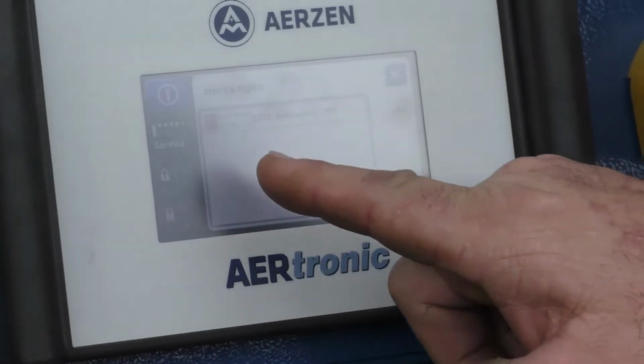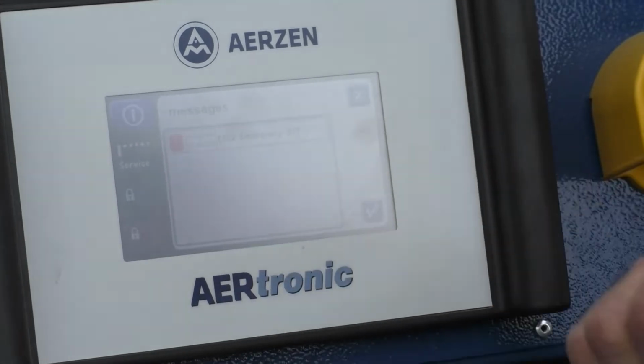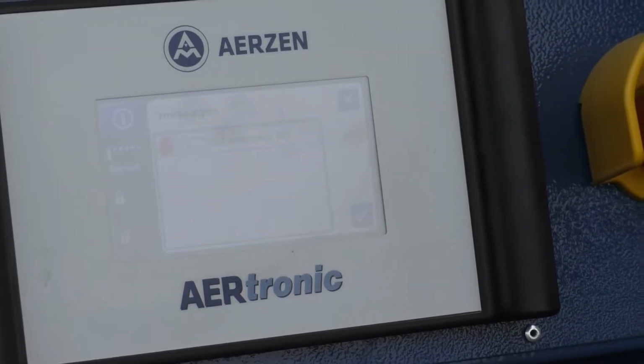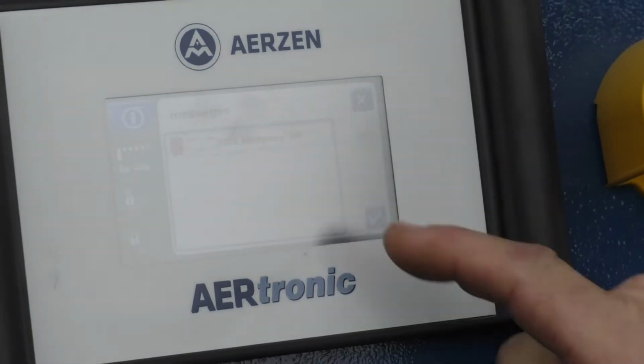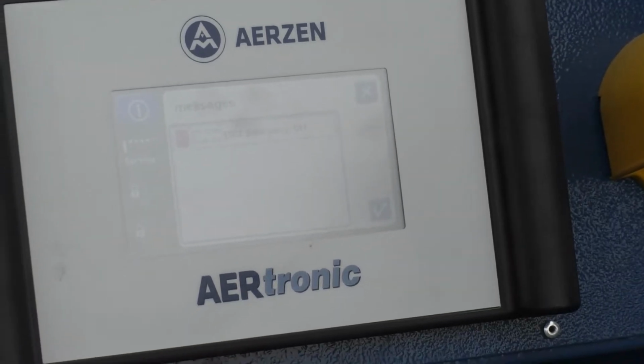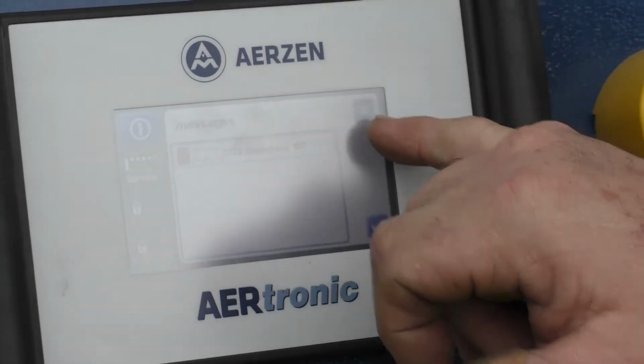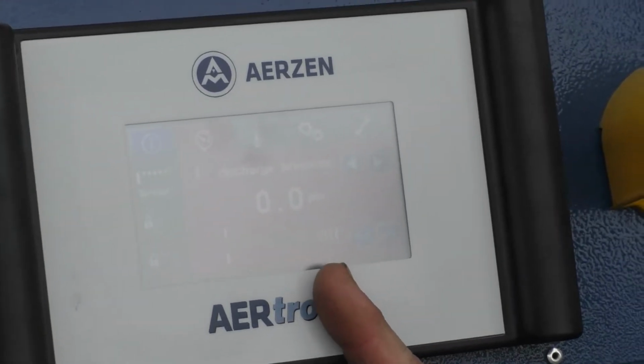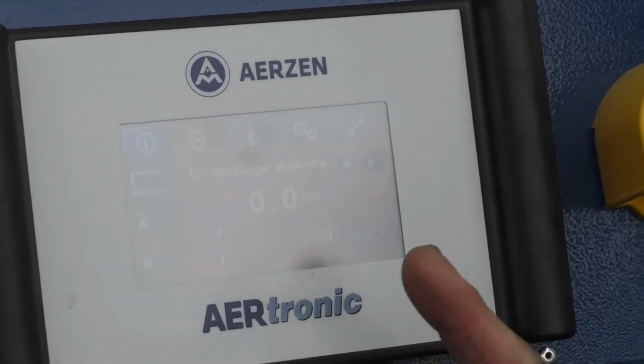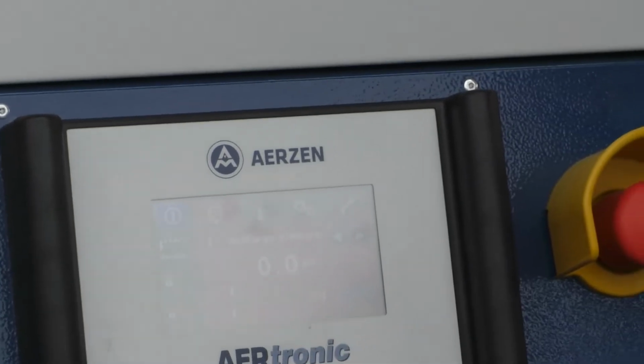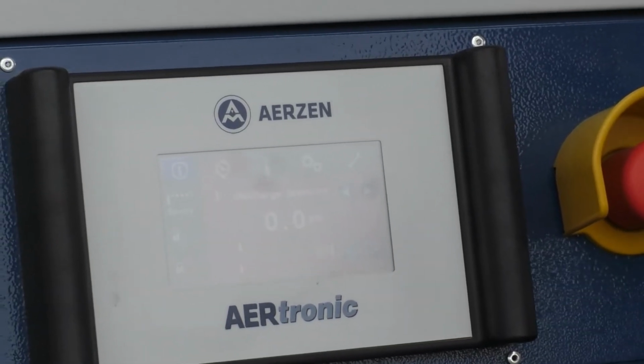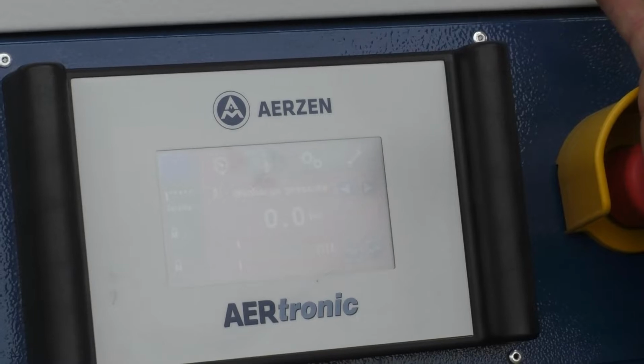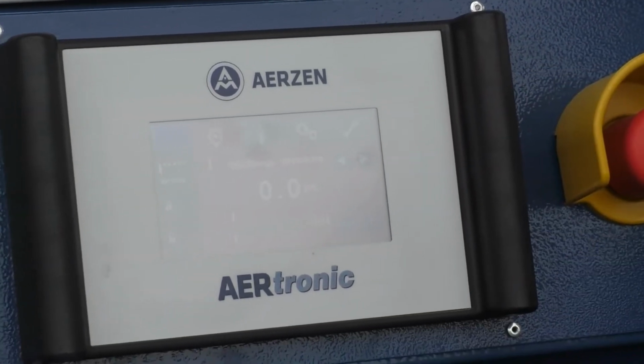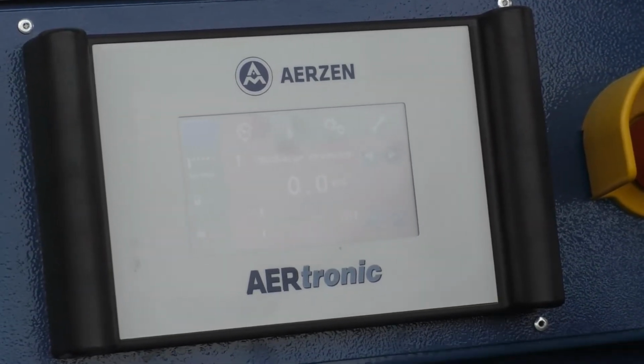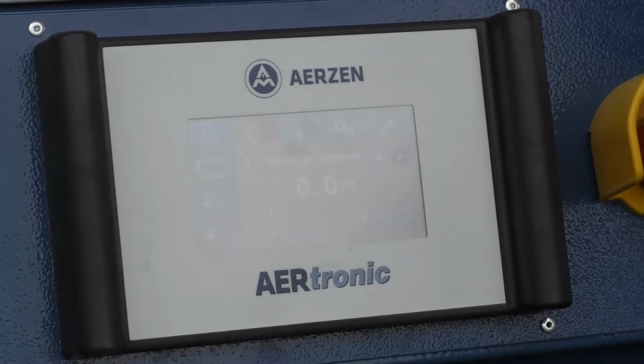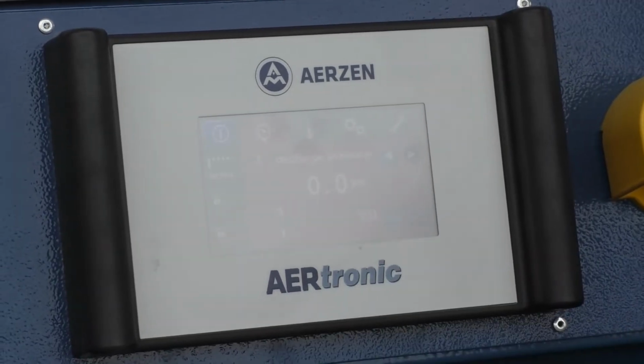To acknowledge it, if you also notice, the little red block, just like the screen, is blinking. If I acknowledge it, but the fault is still present, it just goes solid. So if I exit out of that, now instead of blinking, it's just solid. Now I believe it's after 5 minutes, for a service indicator, it will go back to flashing until that service has been done and you've acknowledged that maintenance interval. But a fault, it'll stay red until that fault's cleared.